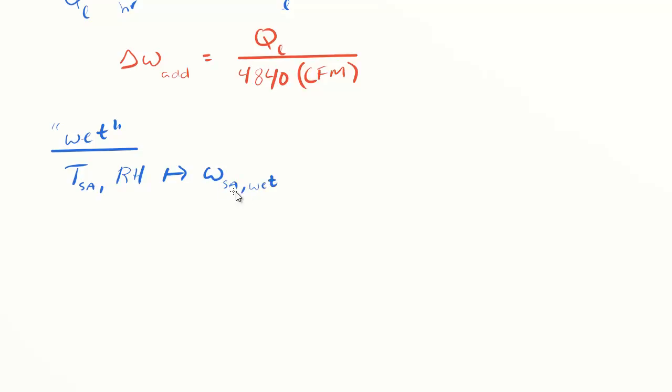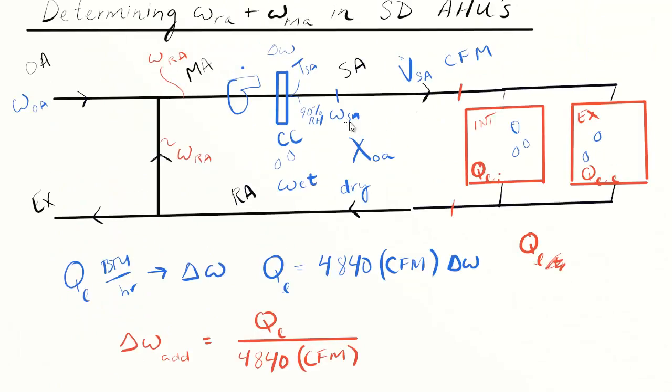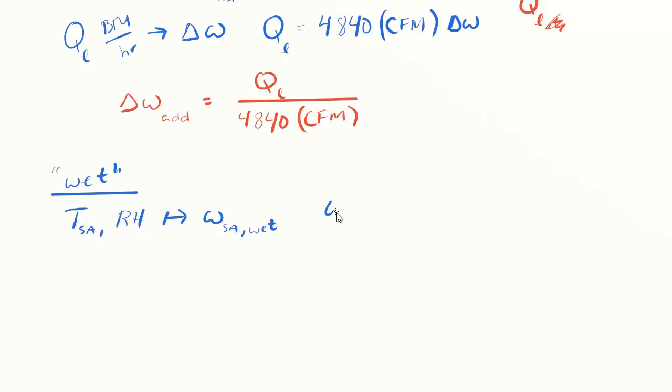I'm going to use omega supply air under the wet condition. If we assume the coil is wet, we automatically have set this humidity ratio. That makes solving for omega return air straightforward. All we have to do is use the omega of the supply air plus that delta omega we added in the space.